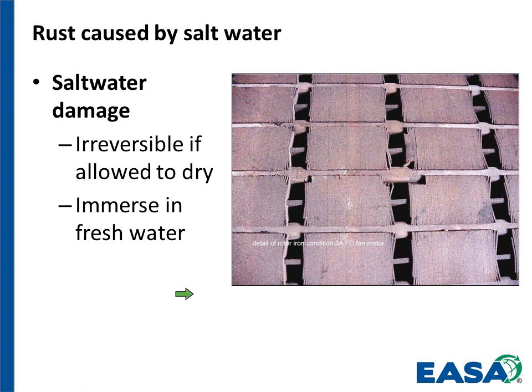So if we look at the vent duct, the airflow through this rotor comes through the underside and then is expelled out through these vent ducts. In the upper portion, we can see missing laminations. We can see swelling of the core here. But the underside of the rotor, if we look down deep beneath these vent ducts, is in most cases more swollen, more damaged, and restricting the airflow far more than what we can see here on the surface. And as you can see, what's on the surface doesn't look good.